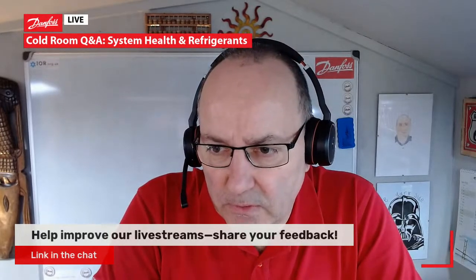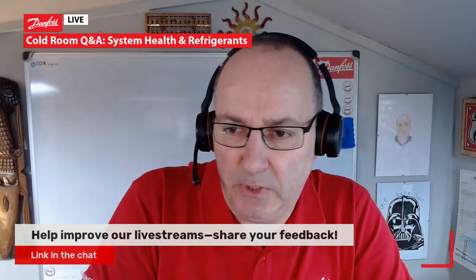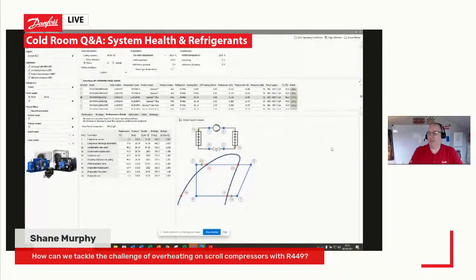Okay, so Shane has put a question up. How can we tackle the challenge of overheating on scroll compressors with 449? Very good question, Shane. 448, 449, we do tend to run quite high discharge temperatures with those refrigerants. And I'll just share my screen again for Danfoss Cool Selector. And you'll see when that comes up on the screen there, again, very, very good way to see what our discharge temperature should be. Now, this is estimated at 77 degrees, which is absolutely fine.